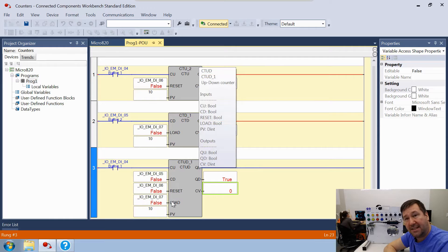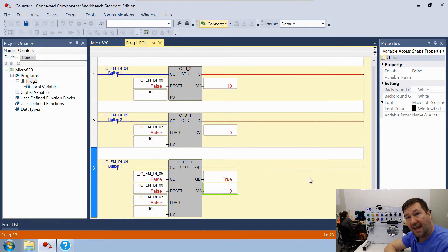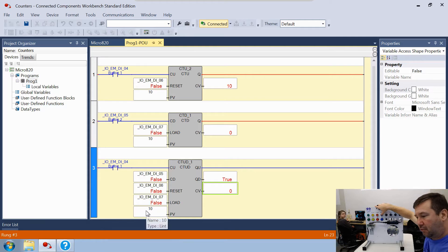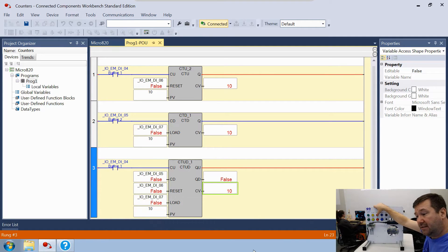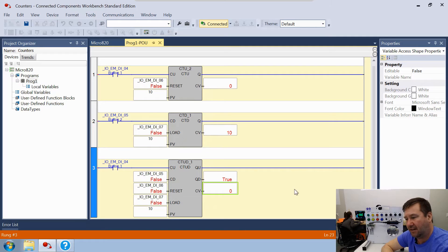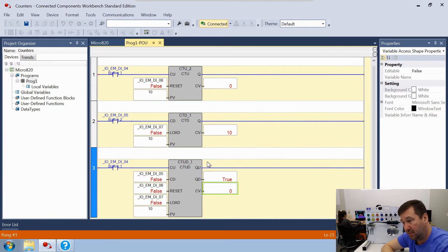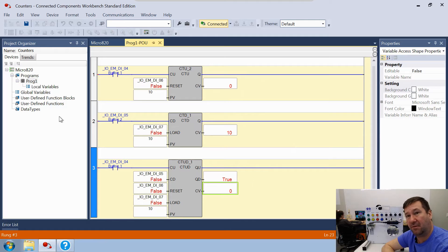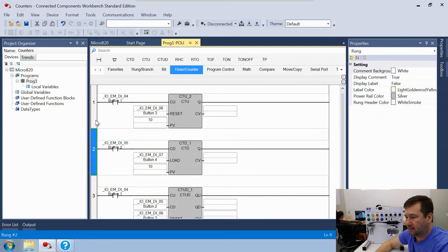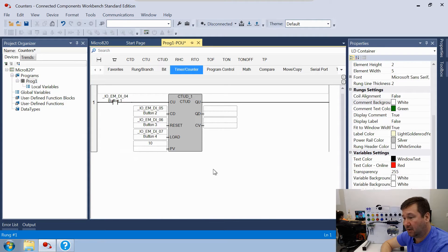The Reset and Load on the CTUD work exactly the same as in the CTU and CTD: Button 4 loads the preset into the counter value, and Button 3 (Reset) puts zero into the counter value. Since CTU's Q maps to QU and CTD's Q maps to QD on the CTUD, we can use just this one counter for the rest of the exercise. Let's disconnect, delete Rungs 1 and 2, and leave the CTUD rung as-is.